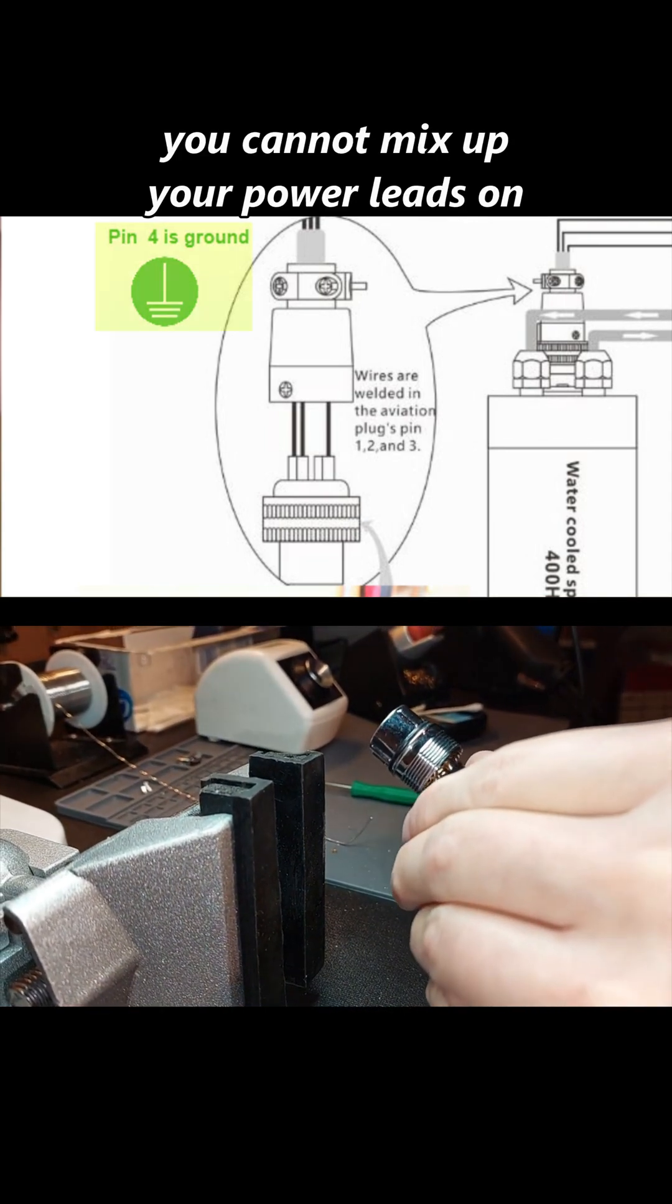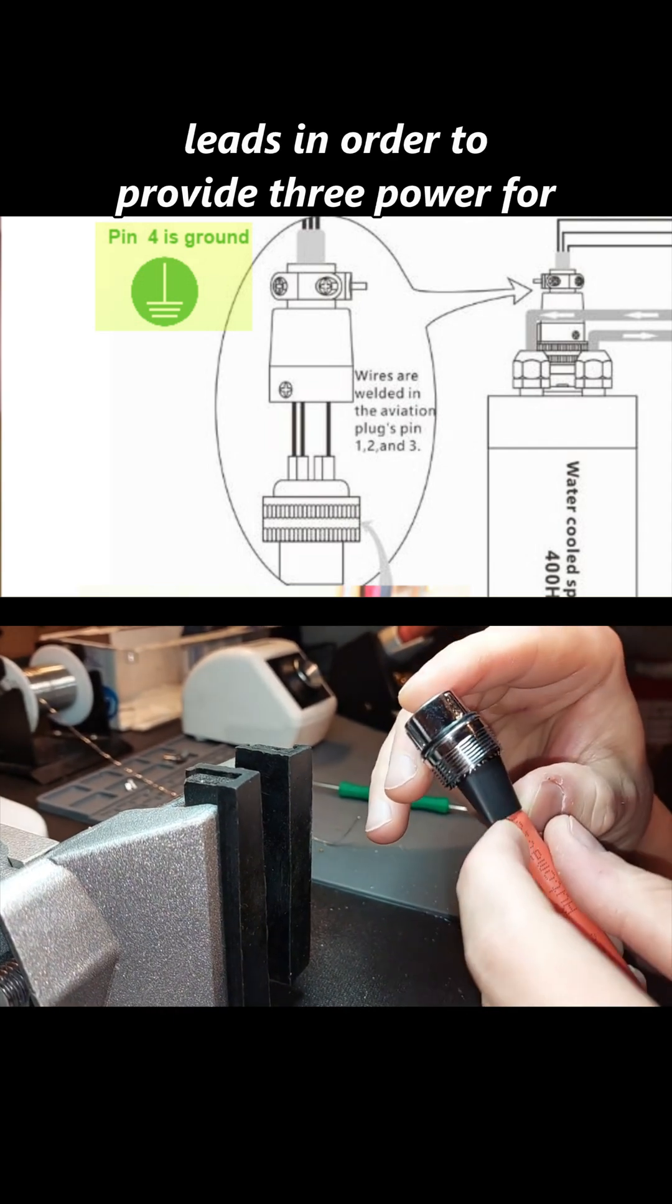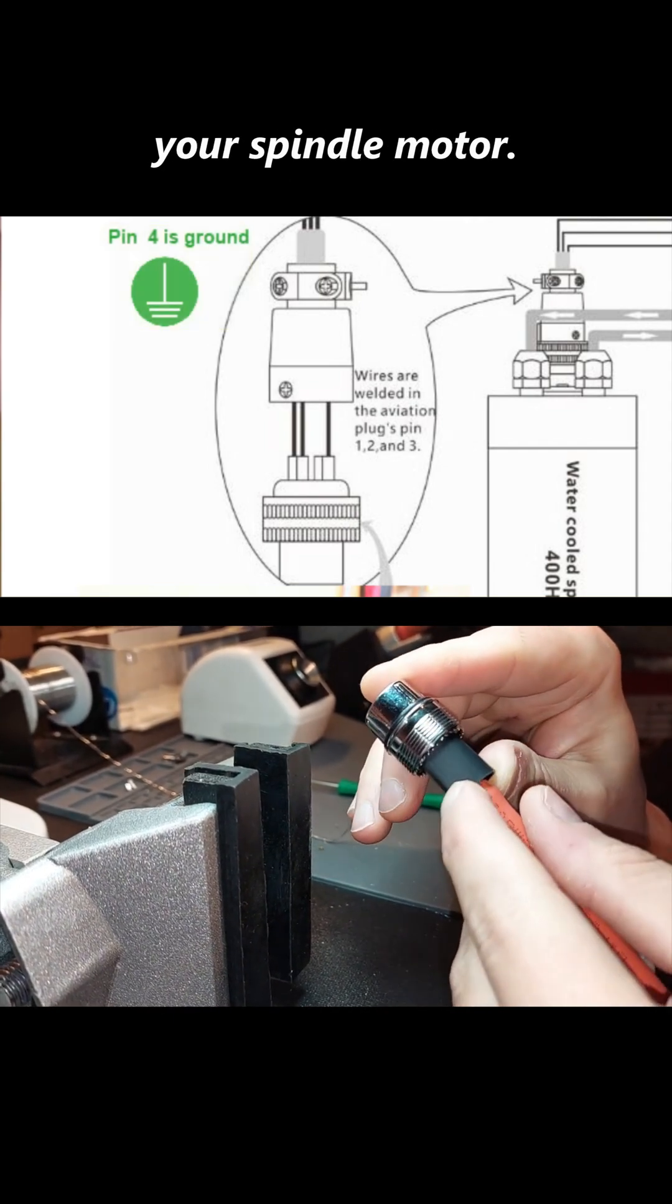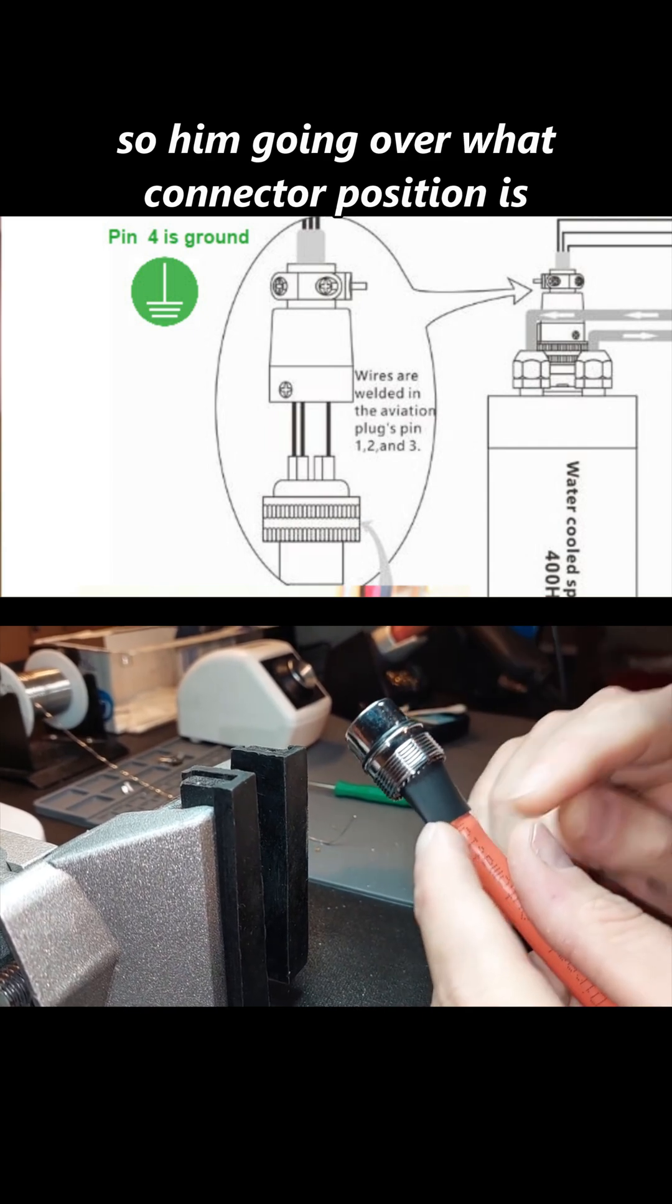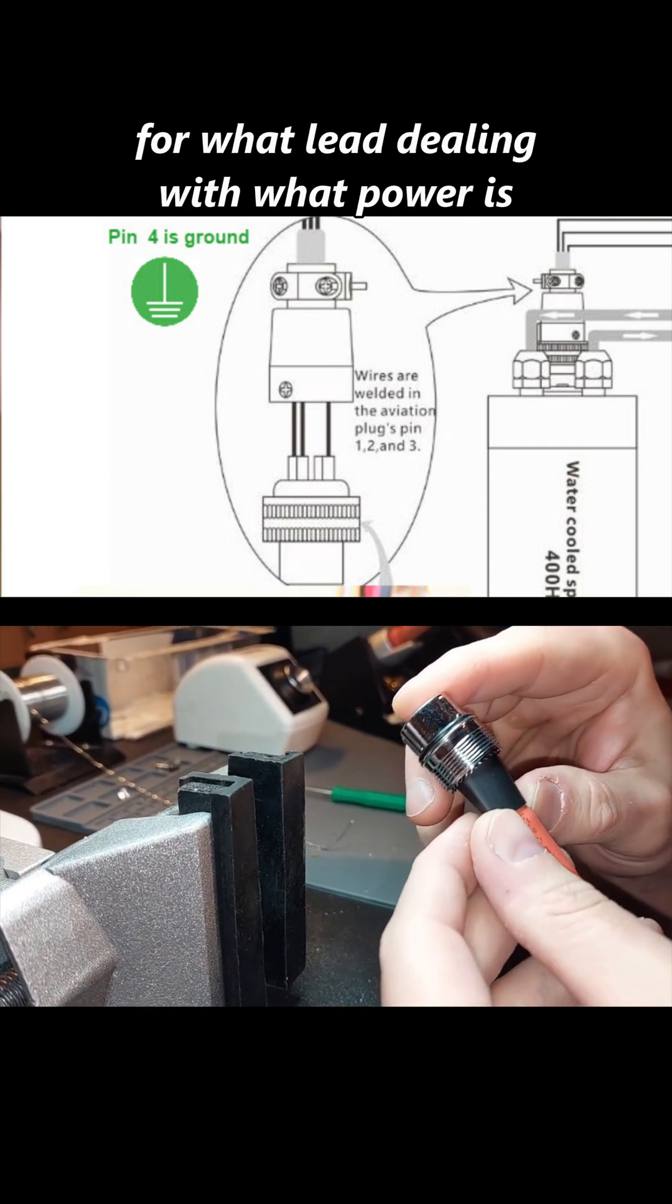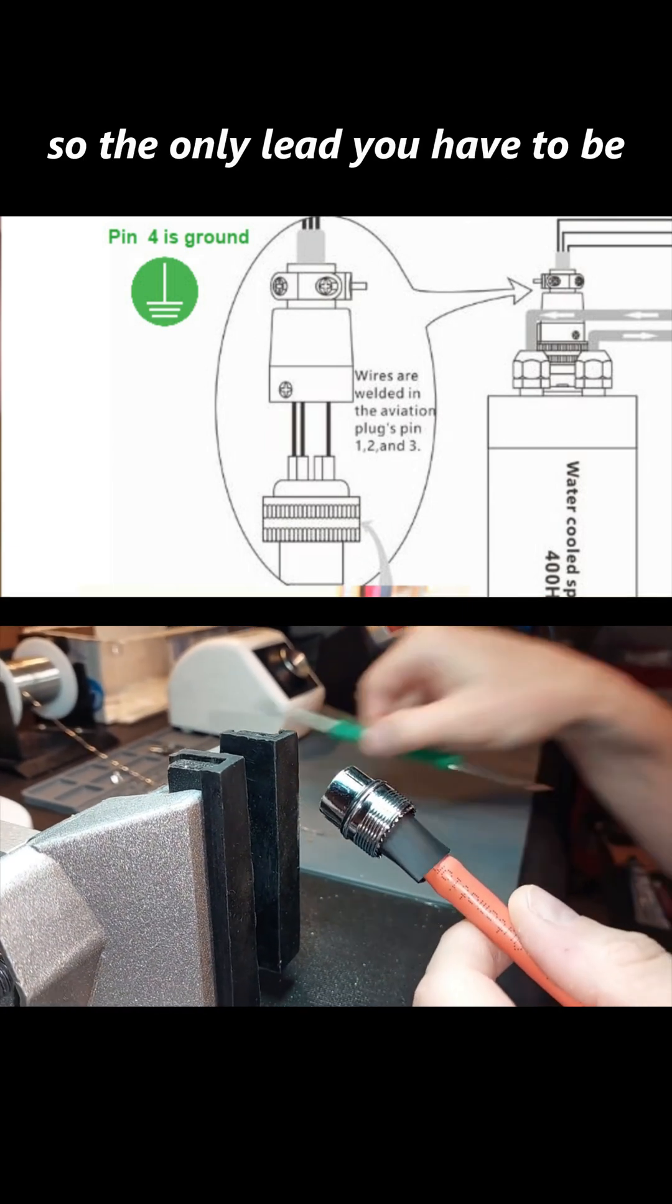You cannot mix up your power leads on the remaining three because they are all power leads in order to provide three-phase power for your spindle motor. So him going over what connector position is for what lead dealing with what power is going to the spindle is irrelevant. So the only lead you have to be concerned with hooking up correctly is, of course, the ground.